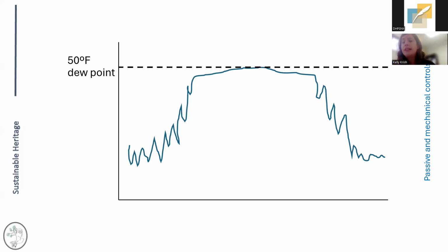The reverse of that scenario is if you find out that your system's capable of a 45-degree dew point, for example. That means that either you'd have absolutely no problem achieving 70 degrees and 50% relative humidity, you could have a lower temperature than 70 degrees and still maintain 50%, you could have a lower relative humidity at room conditions and be able to maintain it, or potentially some combination of lower temperatures and lower relative humidity. So that's a good breaking point. I think we're all fairly familiar with that 70-50 environment. So just to say, depending on where your dew point falls, if it's a higher number than 50, it means conditions that are going to be potentially worse for preservation than that standard environment. Or if it's a lower number than 50, it means you have some opportunities for improved preservation.